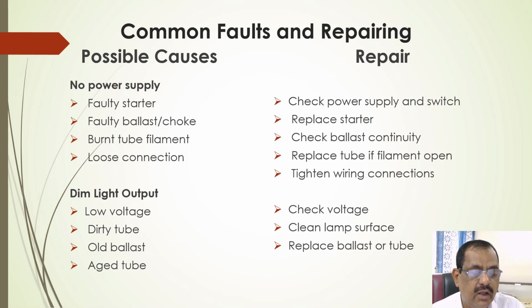Then there is no electron flow. Then the next most common is a loose connection. How does it happen? Because the lamp is fitted in two holders, and if a holder becomes loose, then there is no connectivity, so it will not work. So what you have to do is check the power supply and the switch, whether the switch is working okay or not. Then replace the starter and check ballast continuity. Then replace the tube if the filament is open, and tighten wiring connections and the holders. You have to check whether the pin is sitting properly in the holders or not.